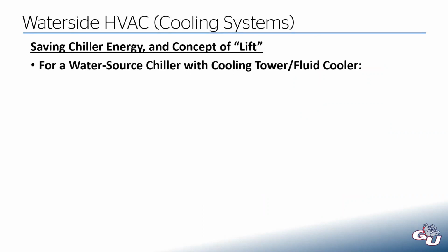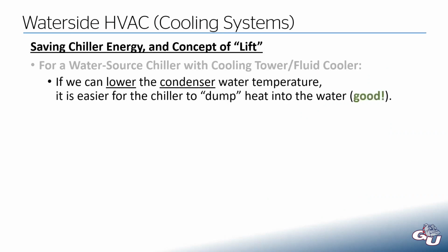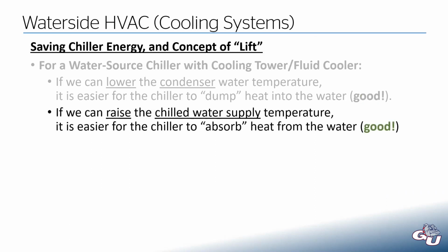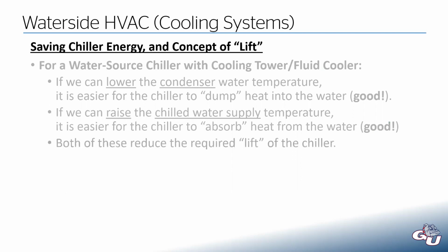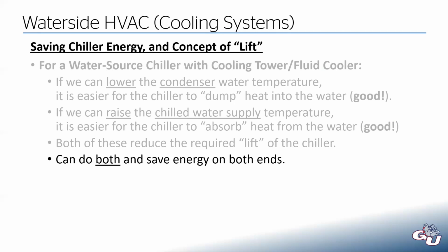If you have a water source chiller with a cooling tower, what if we could lower the condenser water temperature? Then it would be easier for the chiller to dump heat into the water. I mentioned that earlier when I was talking about approach. Or if we can raise the chilled water supply temperature, then it's easier for the chiller to absorb heat from the water, which is also good. So both of these scenarios would reduce the required lift of the chiller. Or we could do both, save energy on both ends of this equation. So fundamentally, if we're able to adjust the conditions that change the temperatures at which we need to run our refrigerant system, we can reduce the lift.